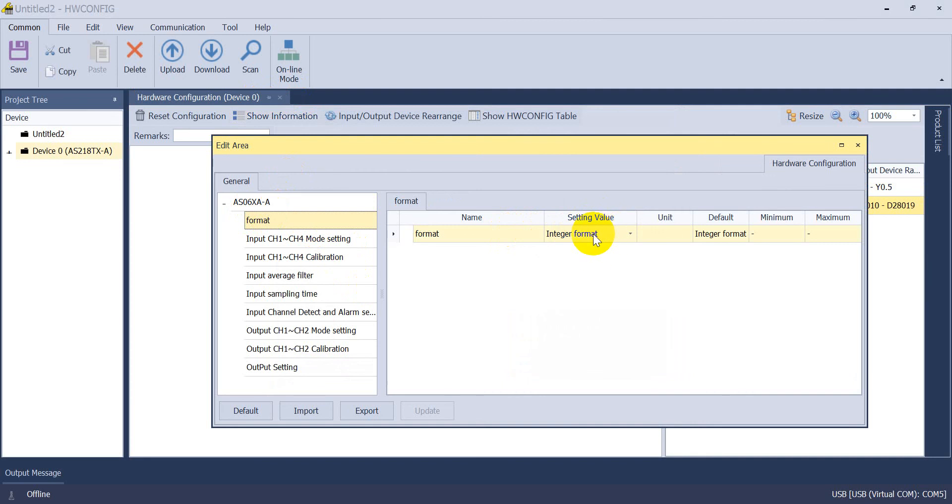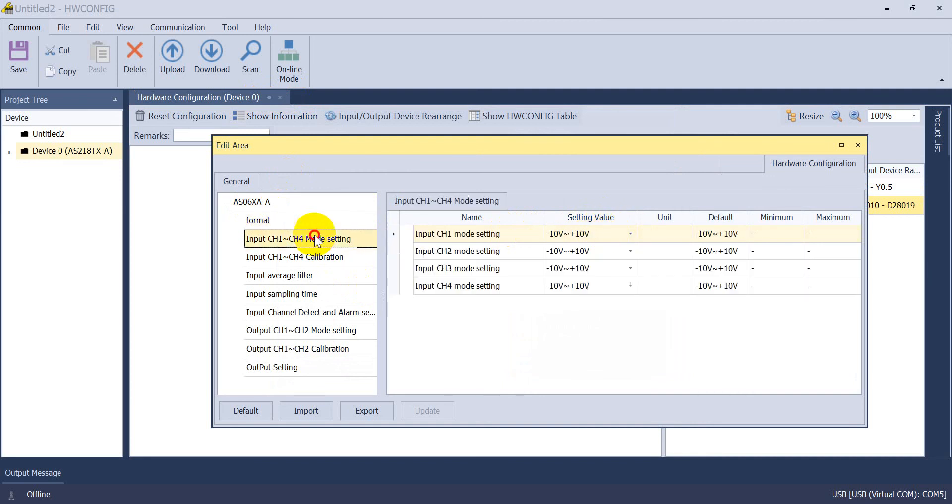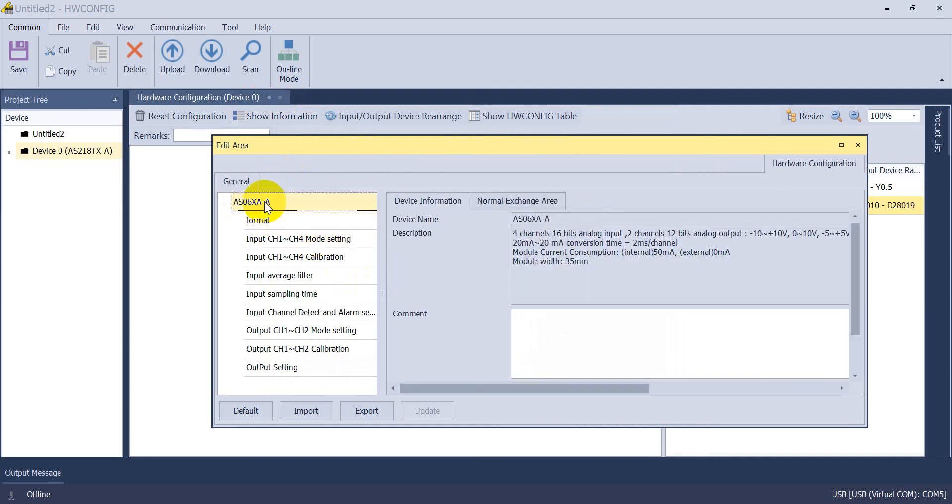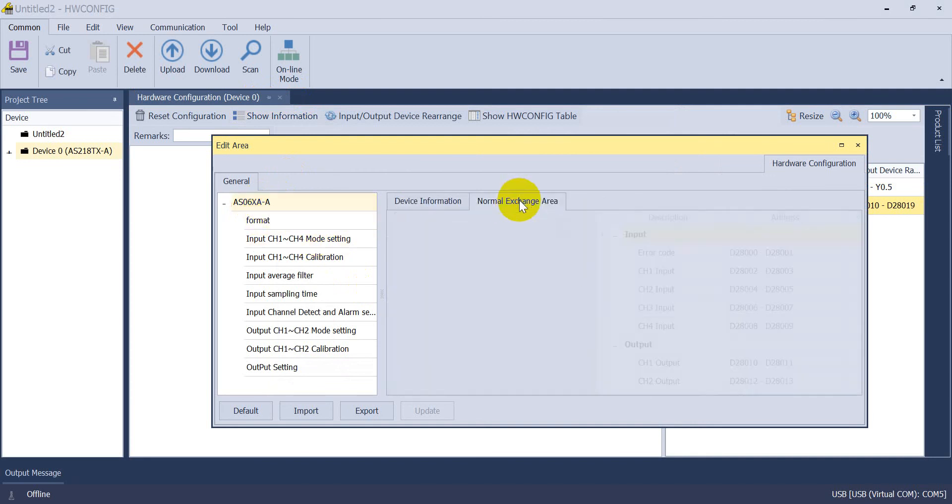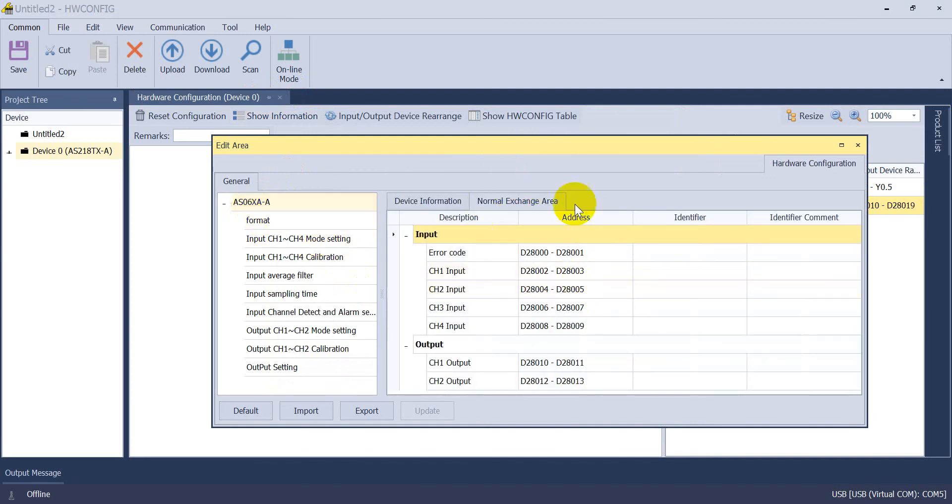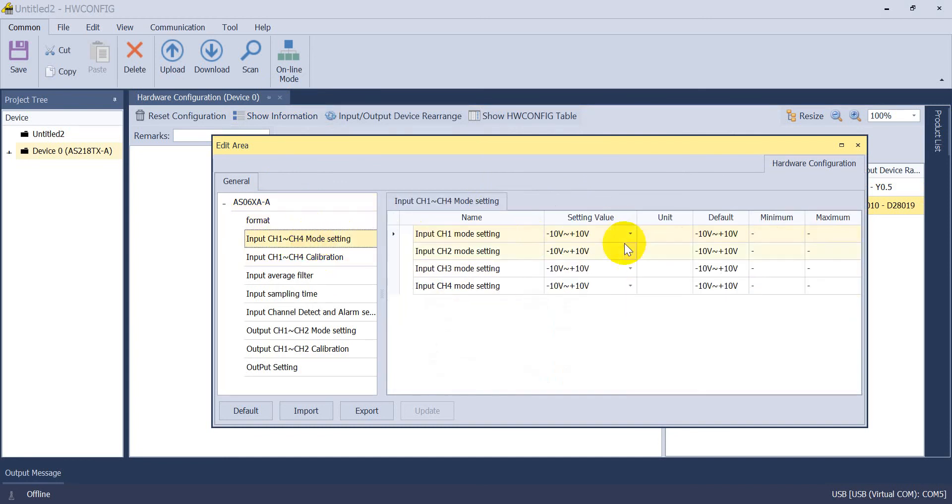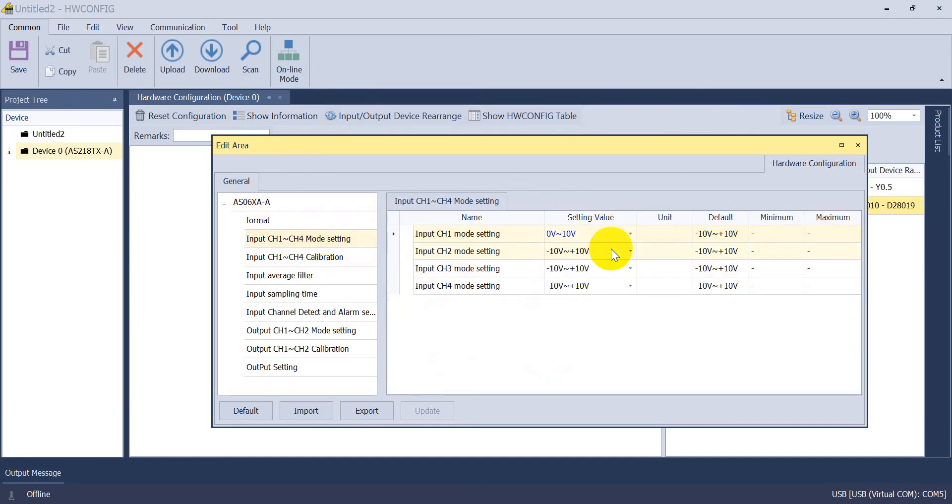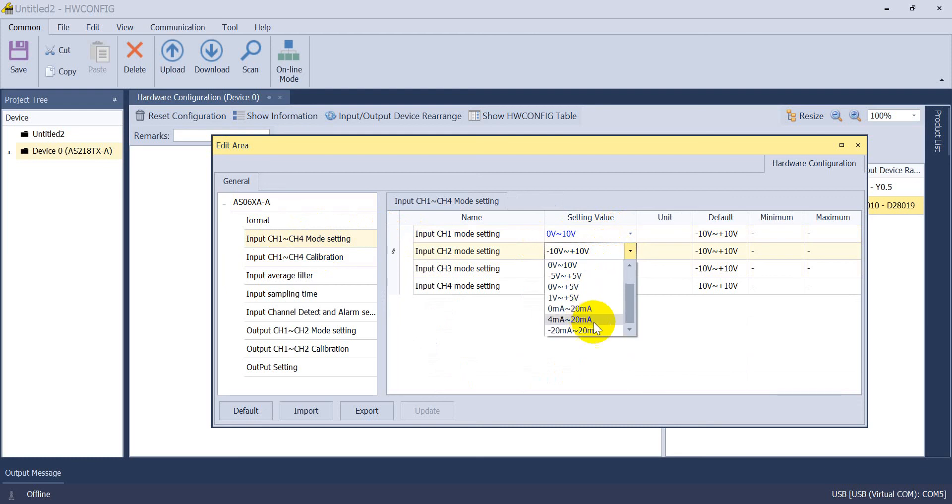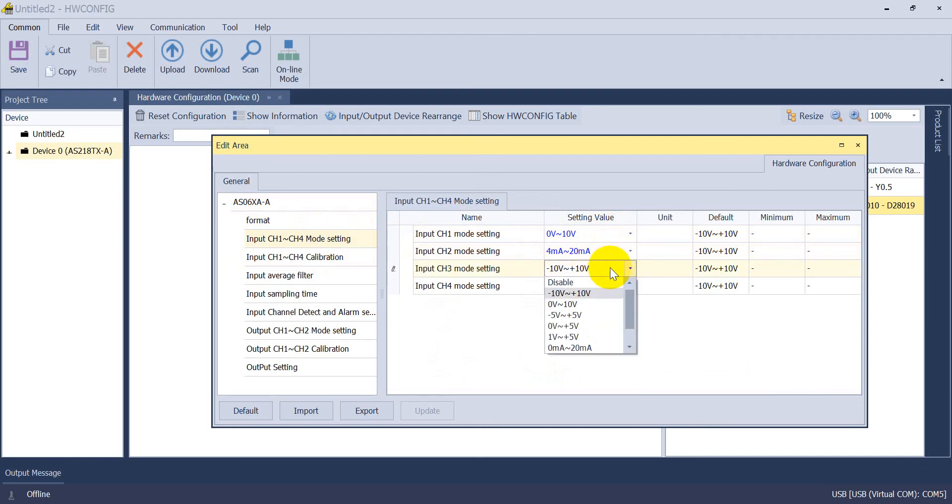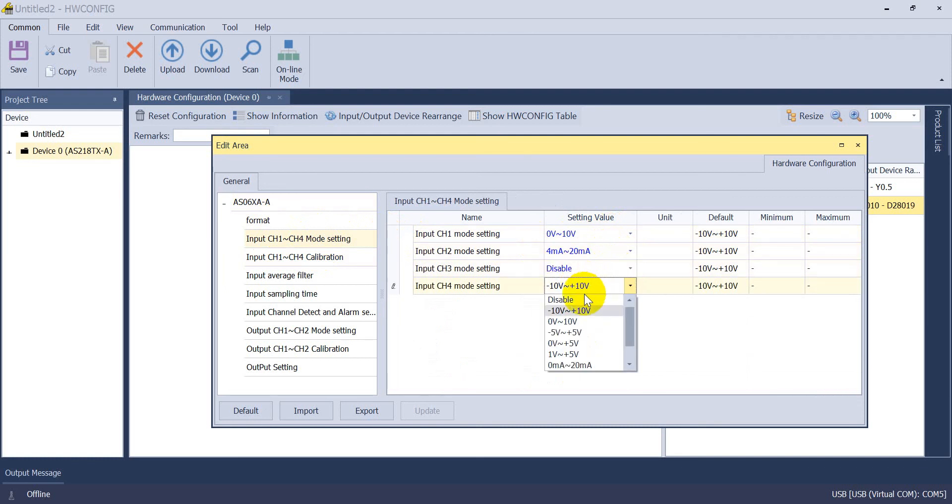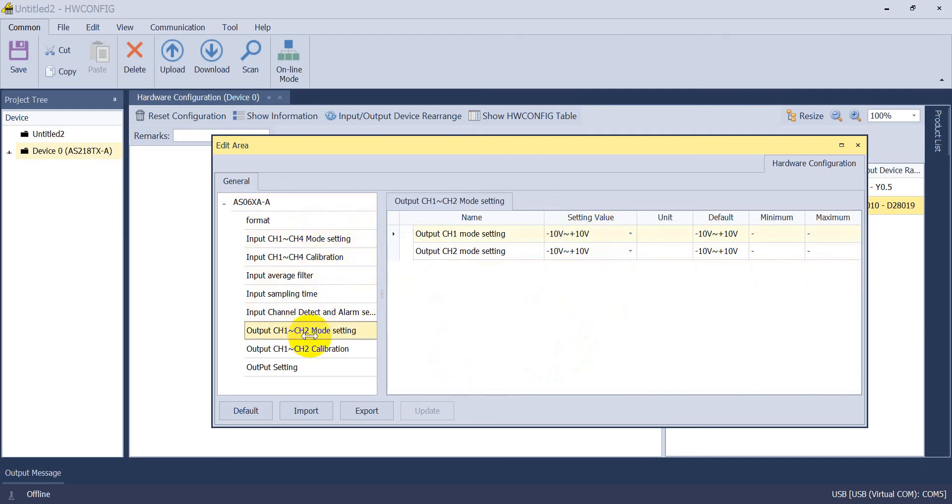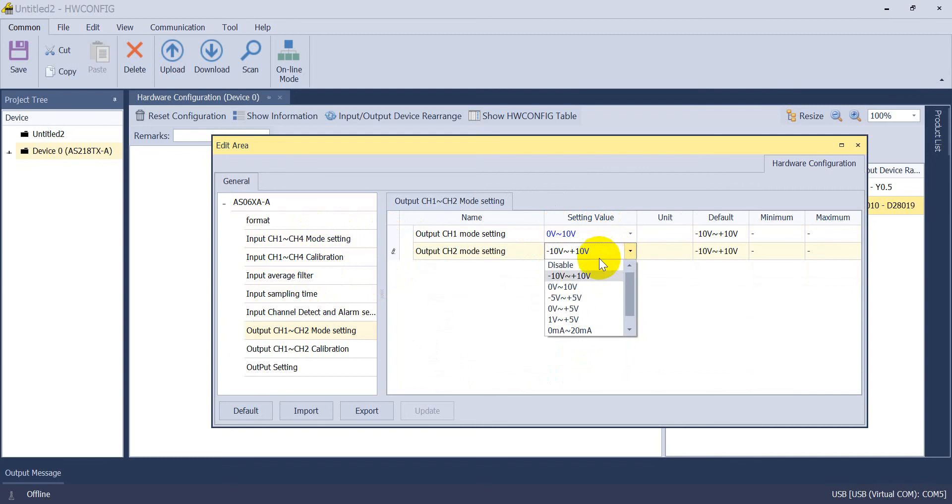First we will try with the integer format. You can see the mapping address, the data register. First we select 0 to 10 volt. For second channel we select 4 to 20 milliamp. For channel 3 and channel 4, because we don't use them, we just select disable. For output we select 0 to 10 and 4 to 20 milliamp.